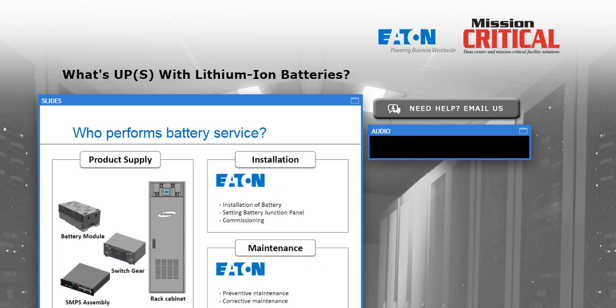Who performs battery service? Most of these batteries are manufactured overseas, and our vendors do have services available locally here in the U.S., but they don't have huge service organizations, and we're seeing a lot of clients procure and deploy lithium batteries. So from our perspective, we're taking over the service of the battery. We'll help with installation, setting the battery system up, commissioning, testing, and as the UPS vendor we'll handle preventive and corrective maintenance if there's a problem in the field.